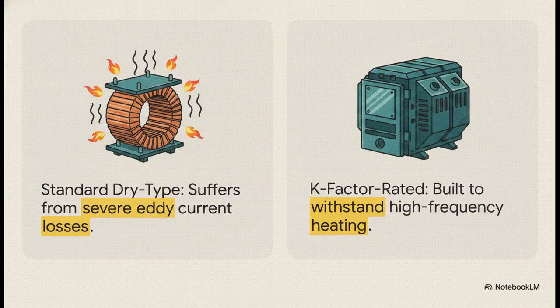Because of all this harmonic punishment, standard dry-type distribution transformers just won't cut it. They suffer from severe eddy current losses, which means the high-frequency noise literally cooks the transformer from the inside out. Not good. To solve this, engineers have to install K-factor rated transformers, like a K13 or K20. These beasts are built with electrostatic shielding, heavier secondary conductors, and modified core geometries that are specifically designed to withstand that intense, high-frequency heating without thermal degradation.